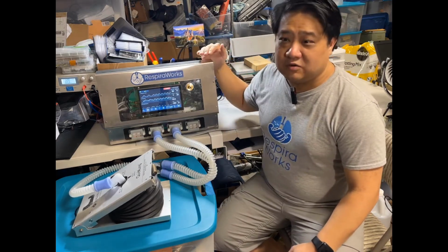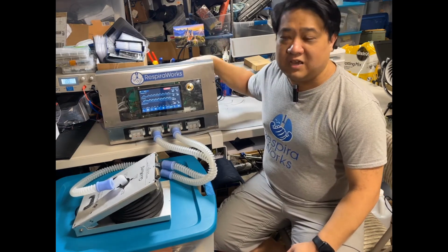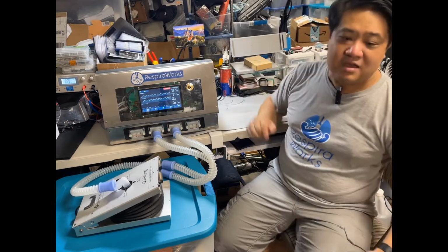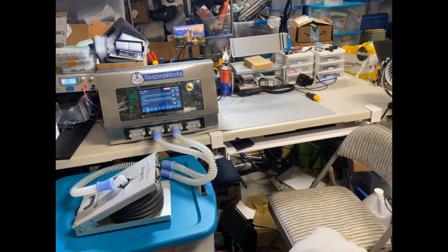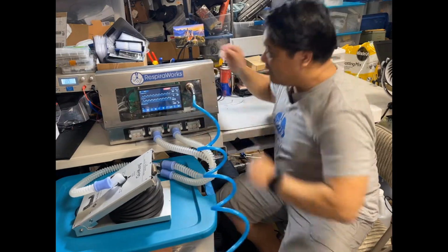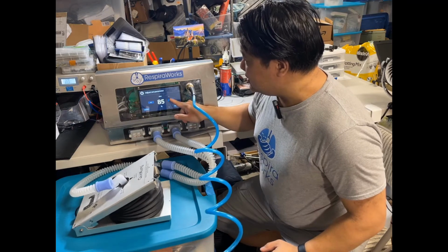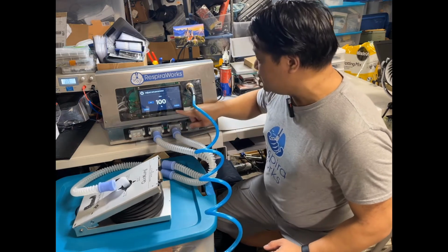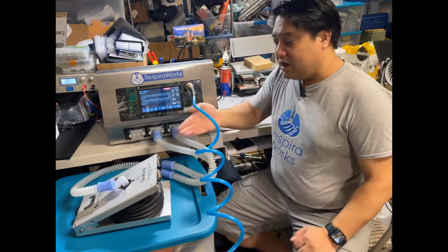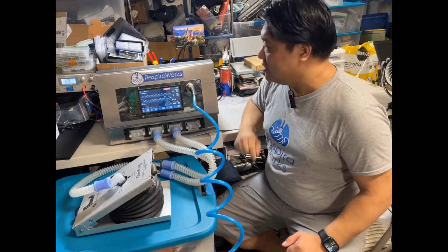Now, if the patient requires supplemental oxygen, the ventilator is also capable of controlling off a standard pressurized hospital oxygen supply at 50 psi. So we actually have a compressed air tank here to act as a stand-in, and I'll go ahead and connect that now. And for demonstration, we're going to set the FiO2 all the way to 100% to demonstrate pure oxygen control. So you hear the blower shut down there, and the vent is now running, delivering to the patient off of the supplied oxygen.